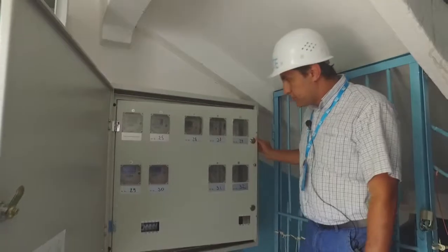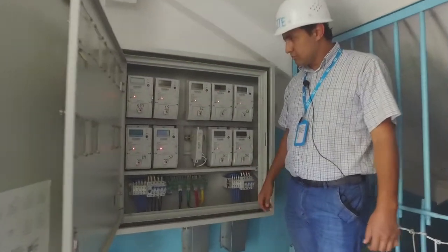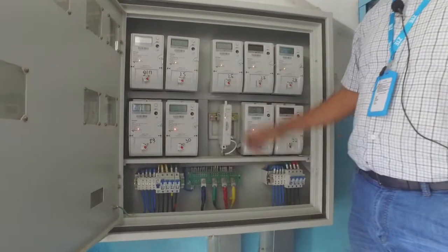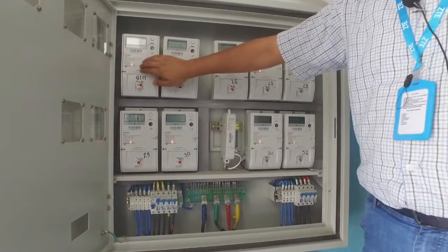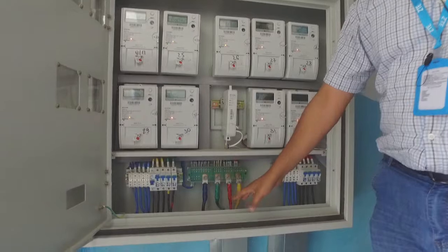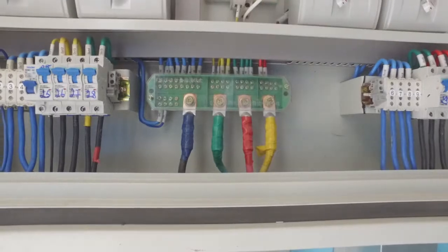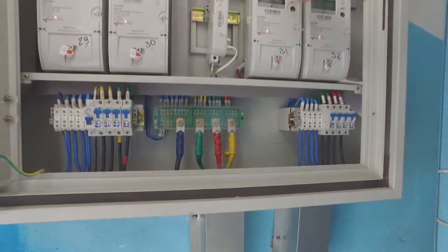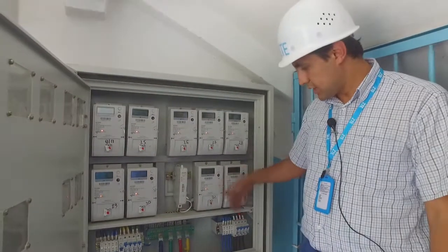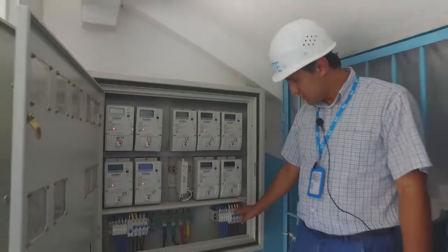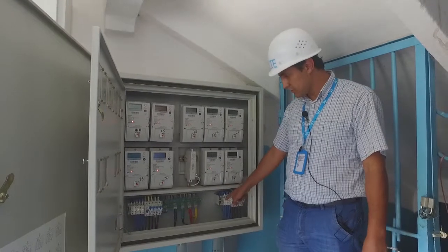Let's continue and open the secondary door. Inside, now you can see inside of our meter box. As you can see here, there are 9 meters, 8 for consumers, and the last one is for lighting. This is the input part. It's coming from the LVDB box, and from here it is distributed to every meter. After the meters get the power from these incoming cables, a sending cable sends energy to the consumer side. These are the MCB switches of consumers, and this is the neutral terminal box.